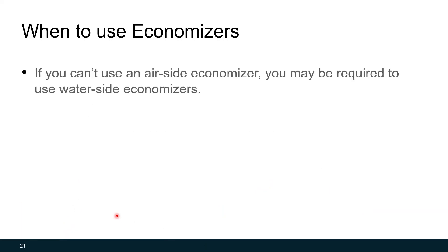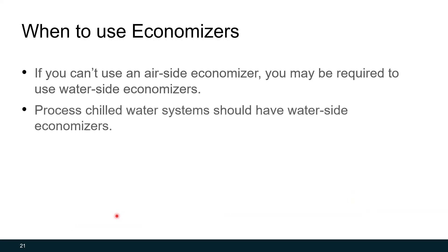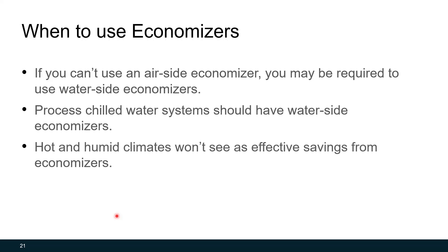If you can't use an air side economizer, you might be required to use a water side economizer. If you have a process chilled water system, you really should have a water side economizer, because those systems are almost always cooling. Note that with building cooling systems, when you can most take advantage of cooler outside air, you're often not cooling the building — and chilled water systems need to supply water at 44 degrees, which is much cooler than the 55 degree supply air of an air side economizer. In a process system like a data center, you're cooling equipment year-round, so a water side economizer makes great sense. Hot and humid climates really won't see effective savings from either type of economizer, which is why there's an exception in the energy code.